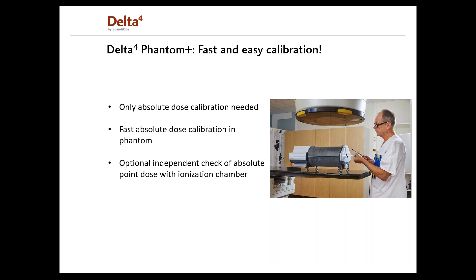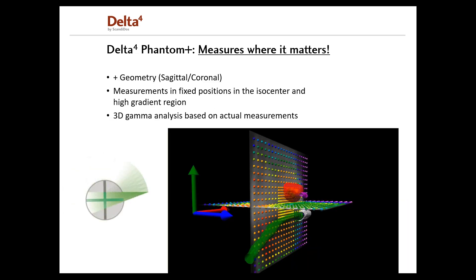Another feature is that the system offers an independent check of absolute point dose. The geometry of the detectors in the Delta4 Phantom Plus has a plus configuration — hence the name Phantom Plus. This is a patented configuration based on two orthogonal detector planes aligned in the cardinal directions in a fixed geometry, providing full coverage of the cross-section of any beam direction. Thereby, the intensity modulation of the treatment delivery can be verified without missing any data.